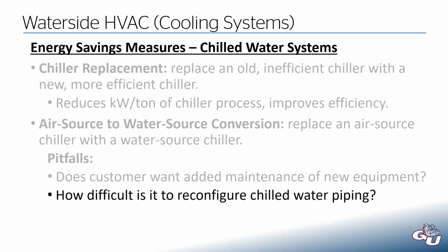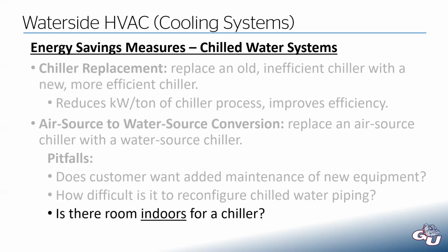You need to figure out how difficult it is going to be to reconfigure the chilled water piping. An air source chiller sits outside of the building. If you go to a water source chiller, you need to move that chiller inside and reconfigure the piping. How difficult is that going to be? It could be simple, or it could be a really substantial cost. Is there even room indoors for a chiller? Chillers can take up a ton of space. So you might not have room anywhere to stick that thing inside your building.